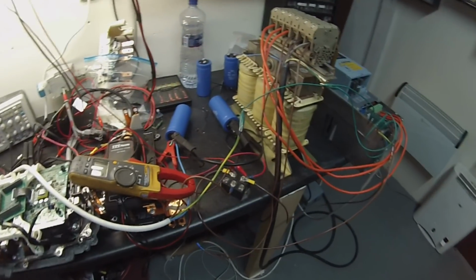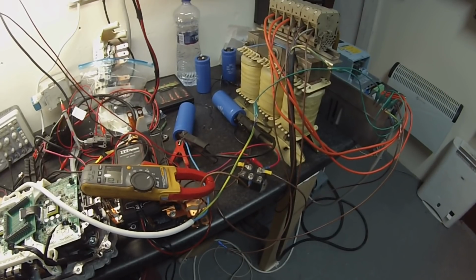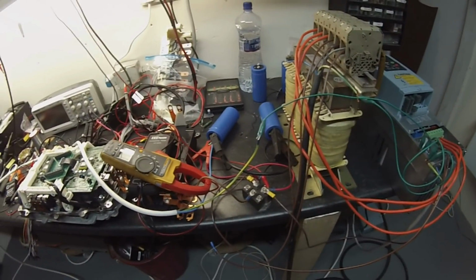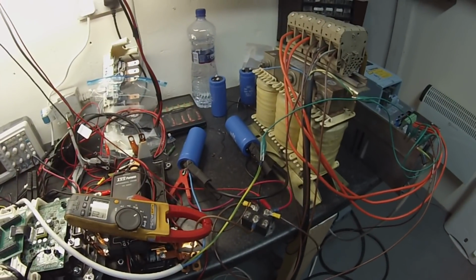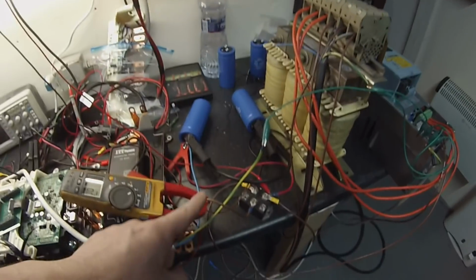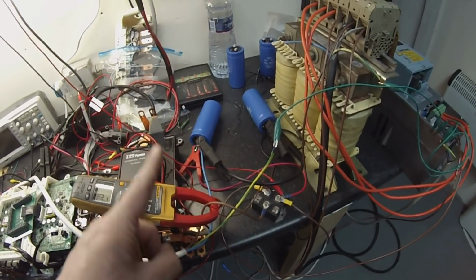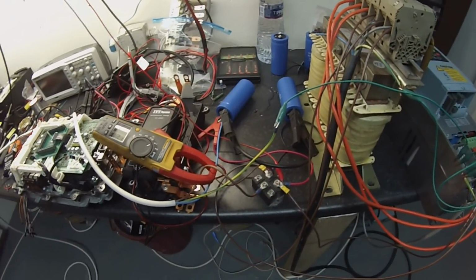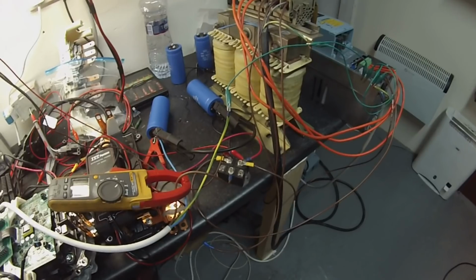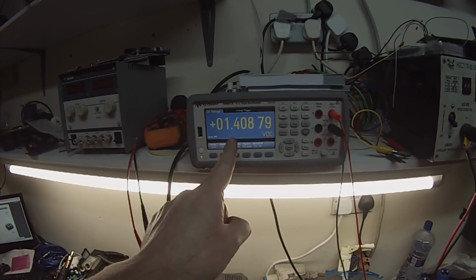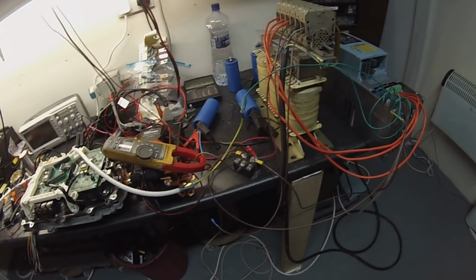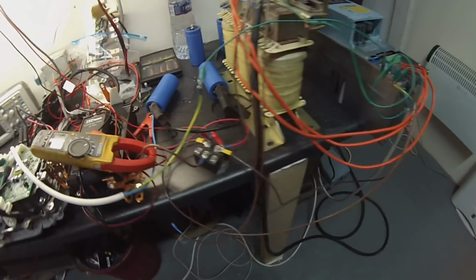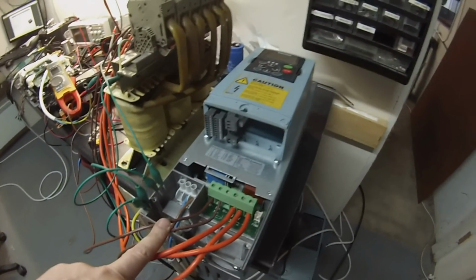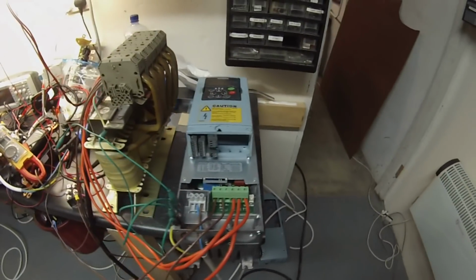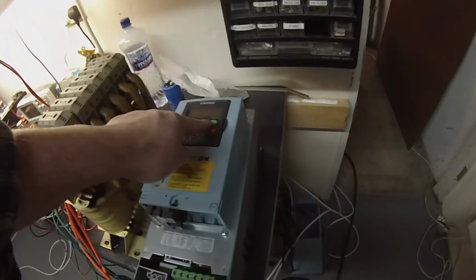Now, this is a device called a voltage doubling rectifier, so it's doing two jobs. Whereas a normal rectifier simply converts AC into DC, this converts AC into DC at twice the normal DC voltage. So when we crank up the power here, we're going to see on the multimeter about 650 volts DC being generated from our single phase 230 volts AC. That's going to be fed into the DC link of the inverter, which will say I've got enough voltage, and then we're going to press the old start button.